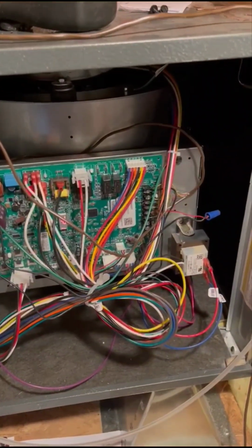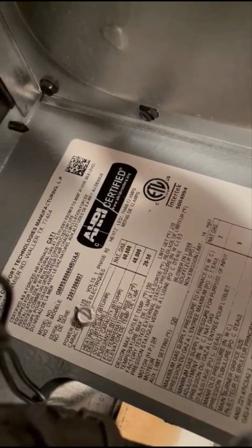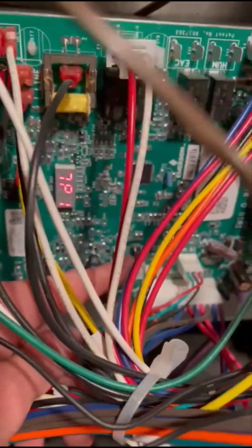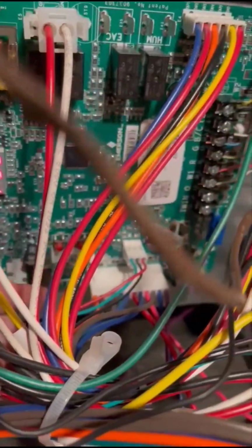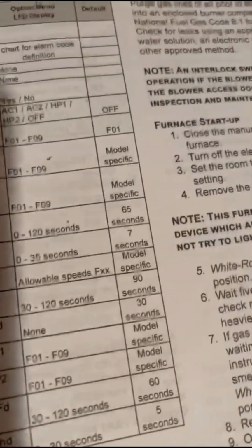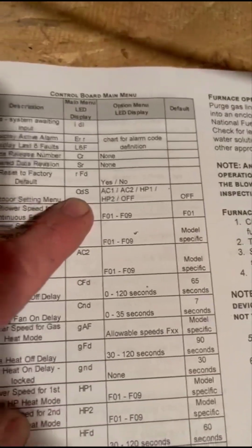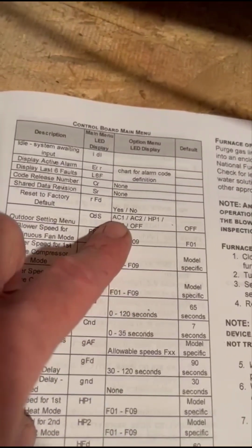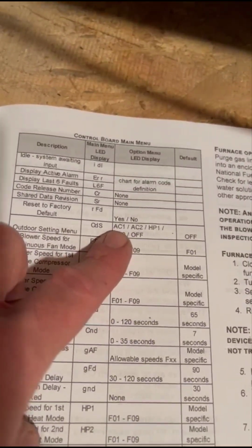Okay guys, today we're gonna go over how to program a GM9S furnace. Very, very common. You have to program the board to make it work properly. And so you have the LED display right here, and you have the push buttons here, option and menu. So basically, when you come over here, the first thing that you're gonna need to do is go to the ODS, because the default setting is off. You have to tell it has an AC. If you don't, it's gonna run very low fan speed.